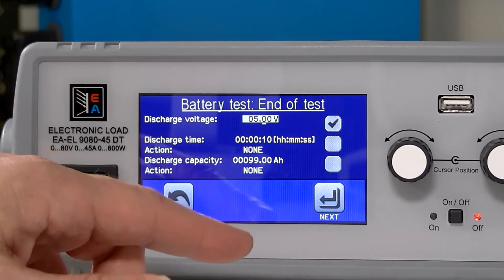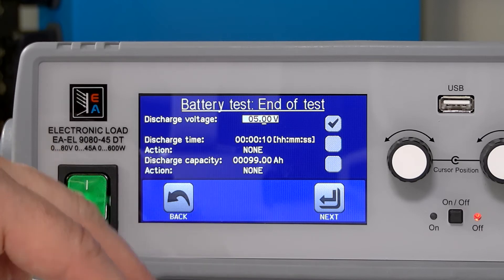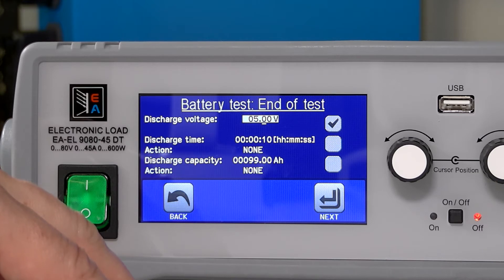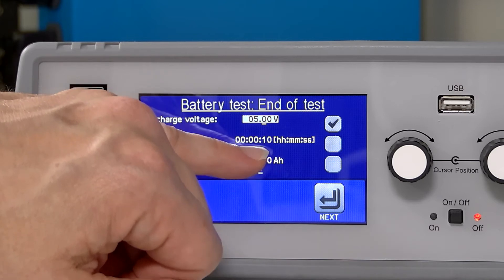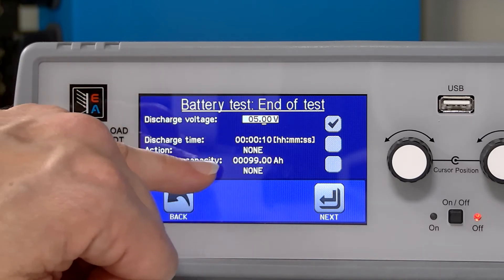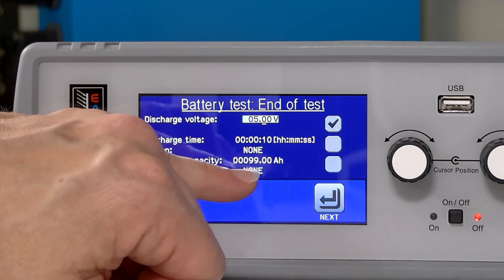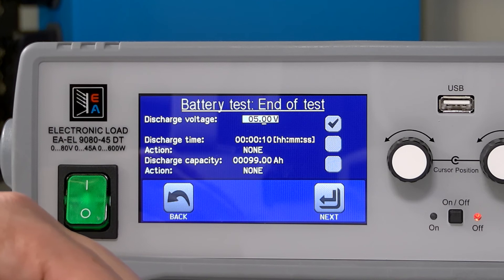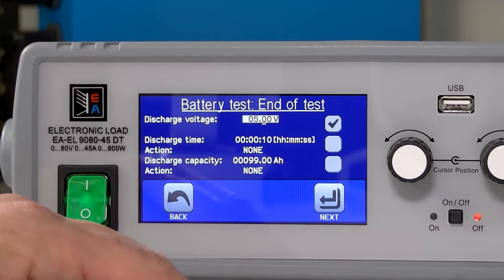The second page is where we're going to define the end of the test. This gives us three different variables to tell us when the test is completed. With a battery, you want to discharge down to a voltage determined by the manufacturer, so you'll have to determine that yourself. You can also give it a time limit for how long you should expect it to run — in this case, 10 seconds. Discharge capacity is more of a protection: if you know you have a discharge capacity of 90 amp hours, for example, you might set it at 99 to ensure the load shuts off around the time it should. And in this case, we're going to discharge down to five volts.